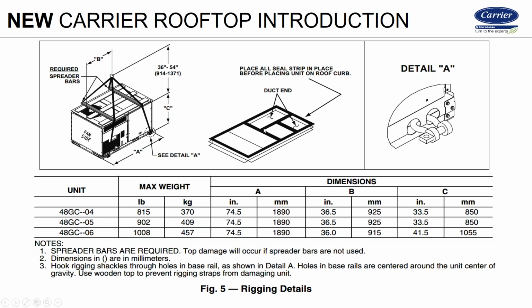And if you don't seal this cross member separating the return air from the supply air, you can get recirculation under here. So that cross member and this cross member, as well as this, all need the seal strip on it. So all this heavy dark line here, that's all seal strip that should be put on the curb. Now that's one thing that happens.